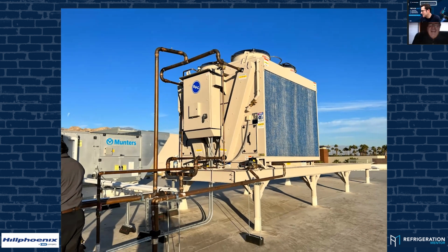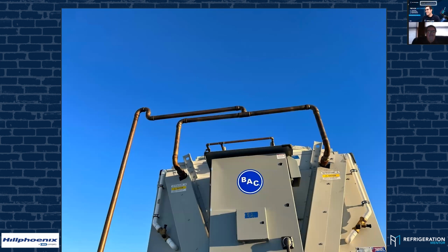All right, so the contractor did a pretty good job here, other than he did bullhead, because whenever you're feeding a condenser or evaporators, if you have 3 evaporators, you want to feed each one of them equally with the same amount of suction pressure return. Here they did the same thing, but they neglected to put a high vent up there. So if you get non-condensables in that gas core, how are you going to vent it? You're going to drill a hole in the top?